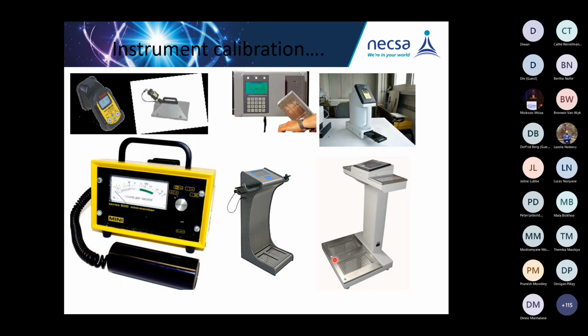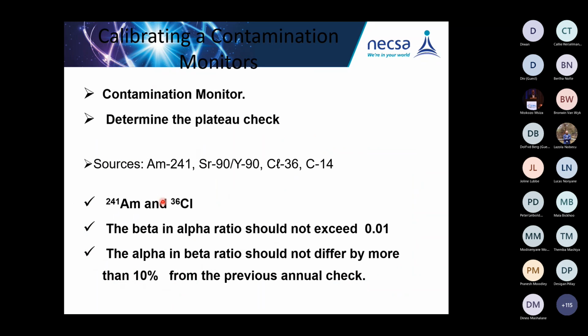These are the hand and foot monitors, and this is another typical example of the instrument which measures surface contamination. That is why you see the units in counts per second. Also, it is very important to know the units. Units for a surface contamination monitor are counts per second or becquerel per square centimeter. If the instrument measures in counts per second, you will have to be able to convert your readings from counts per second to becquerel per square centimeter, because the guideline from ICRP 60 stipulates the levels of radiation in becquerel per square centimeter. That is the reason.